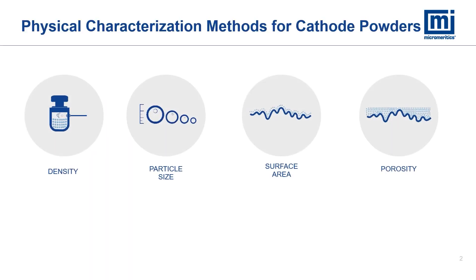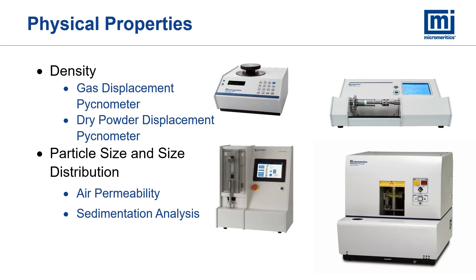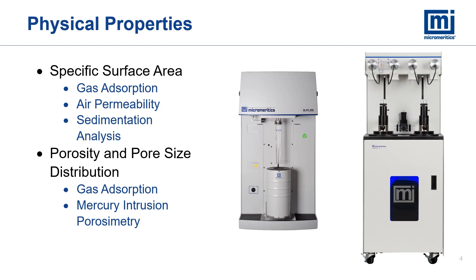The physical characteristics we'll be talking about today are density, particle size, surface area, and porosity. To determine density, we use a gas displacement pycnometer and a dry powder displacement pycnometer. For particle size and size distribution, we use air permeability analysis and sedimentation analysis. For specific surface area, we use gas adsorption, air permeability, and sedimentation analysis. For porosity and pore size distribution, we use gas adsorption as well as mercury intrusion porosimetry.